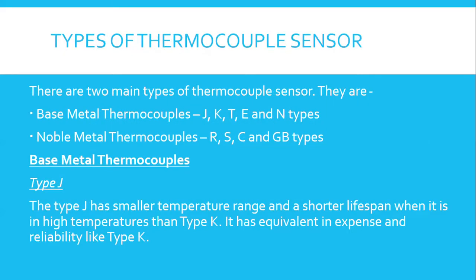Types of thermocouple sensor. There are two main types of thermocouple sensor. They are base metal thermocouples, J, K, T, E and N types, and noble metal thermocouples, R, S, C and B types. Base metal thermocouples. Type J. The Type J has a smaller temperature range and a shorter lifespan at high temperatures than Type K. It is equivalent in expense and reliability to Type K.